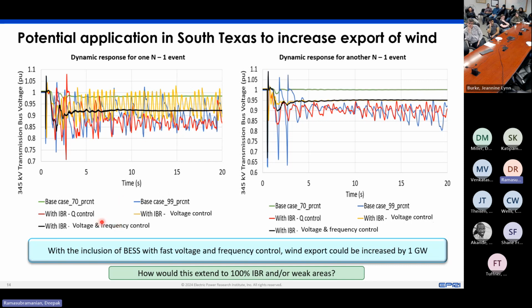So we looked at different options, whether you have to look at it from the perspective of only reactive power, or only fast voltage control. And what we found out was both fast voltage control and fast frequency control were required in order to stabilize the network in this particular region. Whereas in another region of the network, for the same kind of N-1 event, only voltage control was sufficient. It didn't require the frequency control. But if you didn't have either of them, you went into an unstable scenario, as shown by the blue curves.